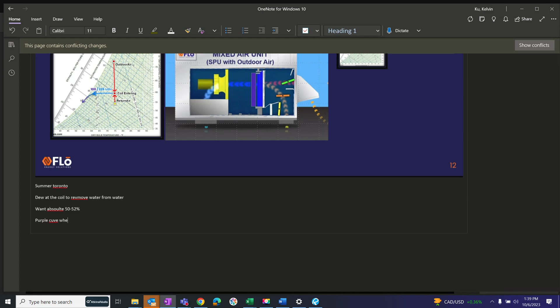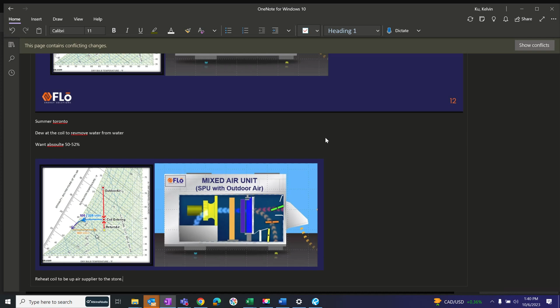So what we do in these units, we put in a reheat coil. That's exactly what I think you were talking about. That coil is there to essentially temper the air, to bring it back up to a neutral temperature that we can deliver to the store. Some of the ASHRAE standards require that you have the capacity to get it back up to 70 degrees. Now, we don't actually need to get all the way to 70, but the units have to have that capacity to do so. And so this is the cycle. You're right. You are cooling, dehumidifying, and reheating to get it back up to a neutral point.